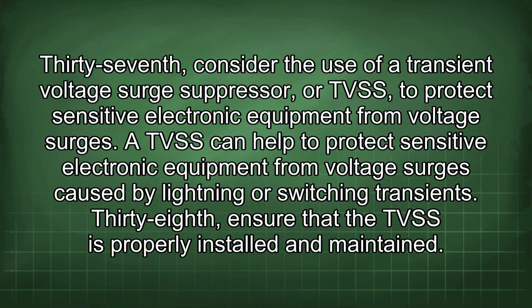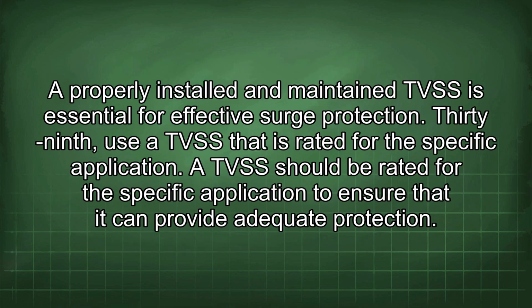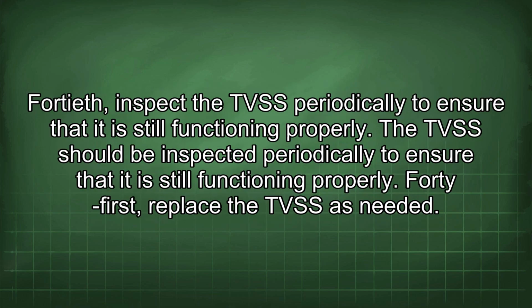37th, consider the use of a transient voltage surge suppressor, or TVSS, to protect sensitive electronic equipment from voltage surges. A TVSS can help to protect sensitive electronic equipment from voltage surges caused by lightning or switching transients. 38th, ensure that the TVSS is properly installed and maintained. A properly installed and maintained TVSS is essential for effective surge protection. 39th, use a TVSS that is rated for the specific application. A TVSS should be rated for the specific application to ensure that it can provide adequate protection. 40th, inspect the TVSS periodically to ensure that it is still functioning properly.